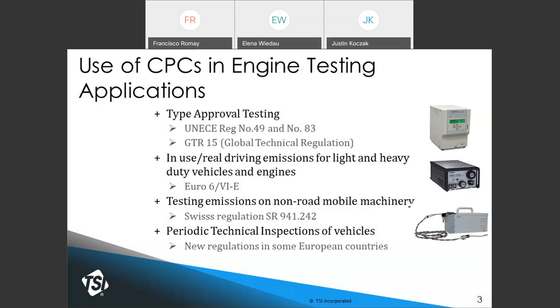A third application is measuring solid particle concentration on non-road mobile machinery — for example, the MPAT, which complies with the Swiss regulation. A new application for CPCs is periodic technical inspection of vehicles. The Netherlands already has a PTI regulation, and these portable instruments can also be based on CPC technology.